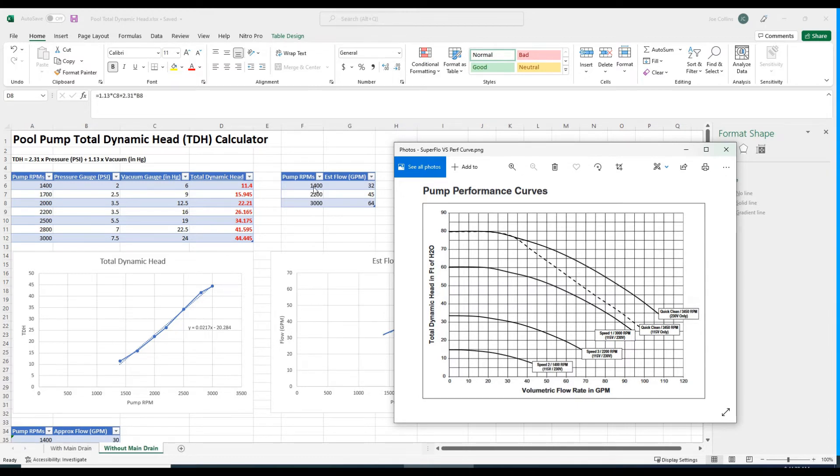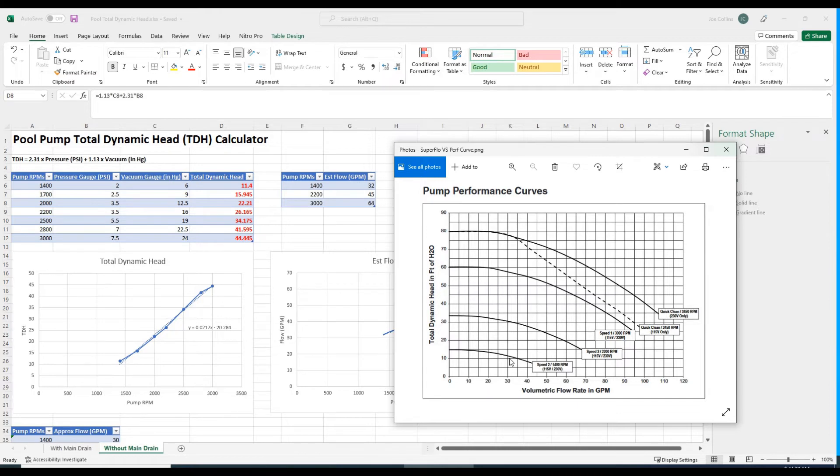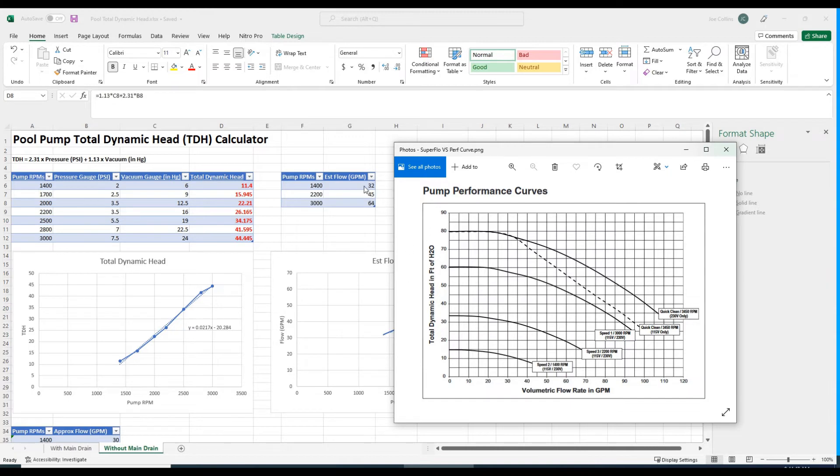Our total dynamic head at 1400 RPMs is 11 feet. Here's 10 feet, so a little bit above that comes out to about 32 gallons a minute. This is subject to your interpretation. At 2200 RPMs, that gives us 26 feet of head, which I estimated to be about 45 gallons a minute.